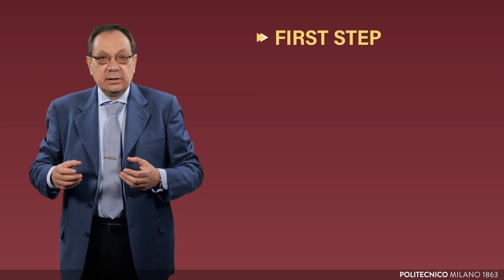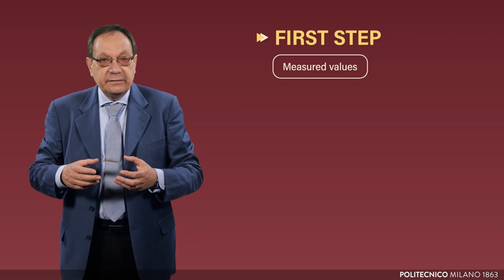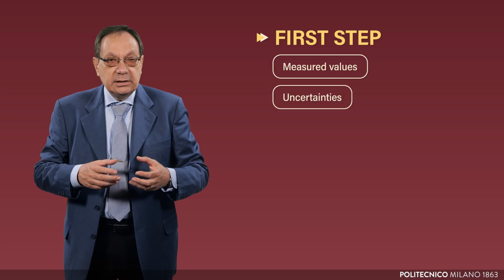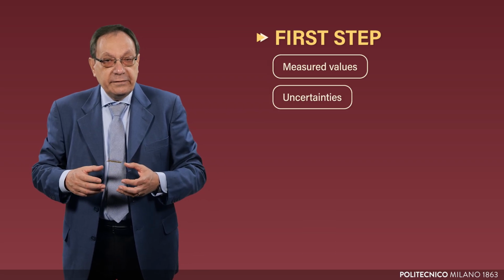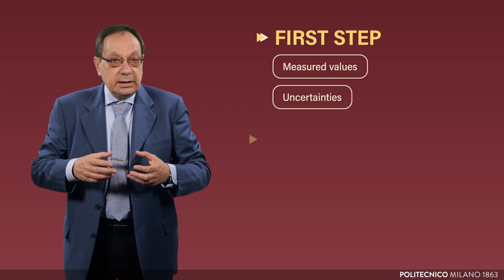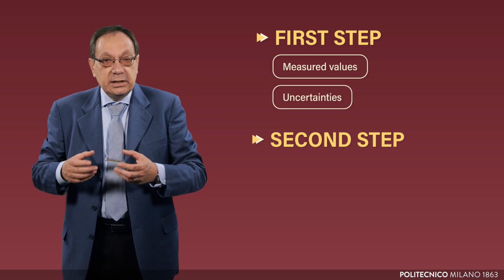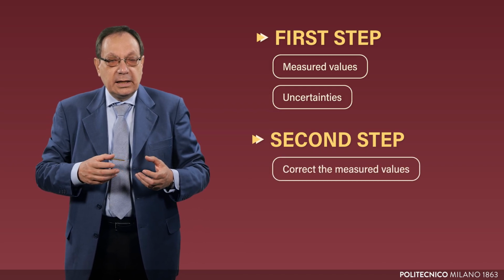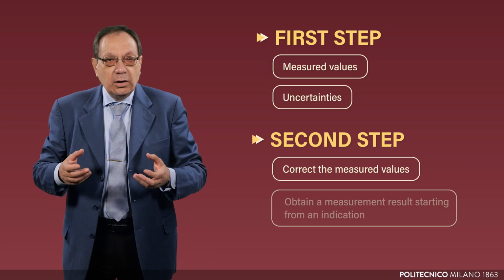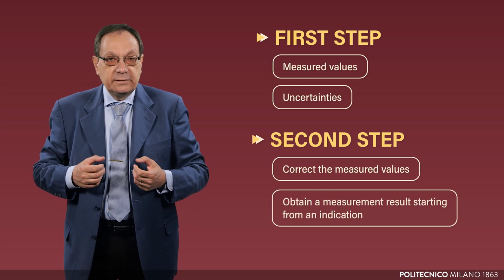To summarize, we have seen with the practical example how to carry out a calibration. The steps we have seen are the essential and most important ones that have helped us to understand what needs to be done in the first step, where the measured values and their respective uncertainties from the instrument under calibration and from the reference are related, and in the second step where these values are used to correct the measured values and, as recommended by the VIM, obtain a measurement result starting from an indication.